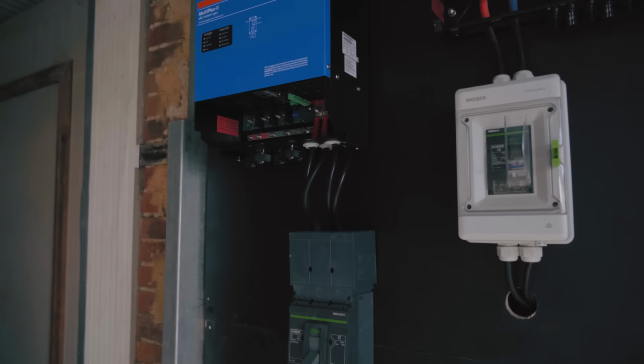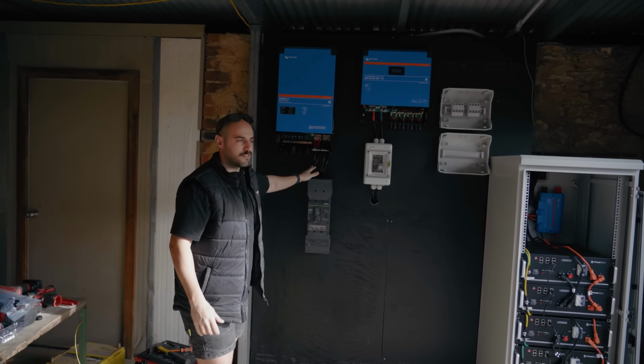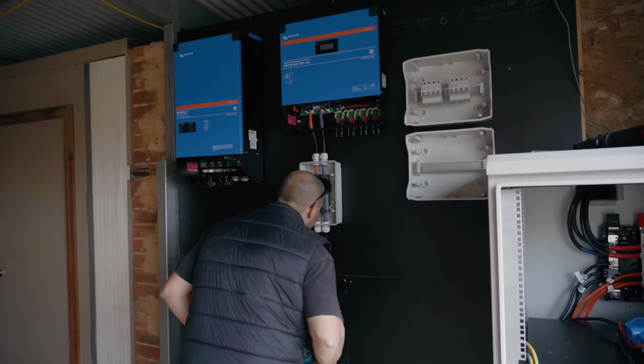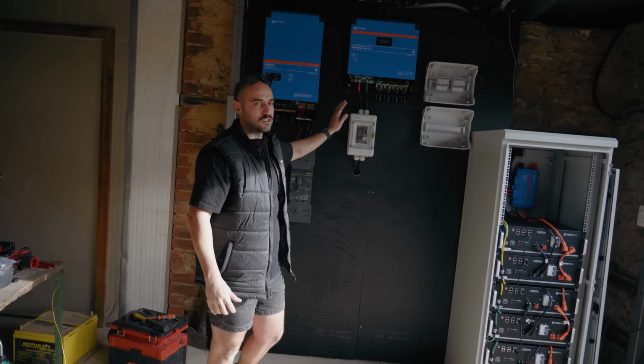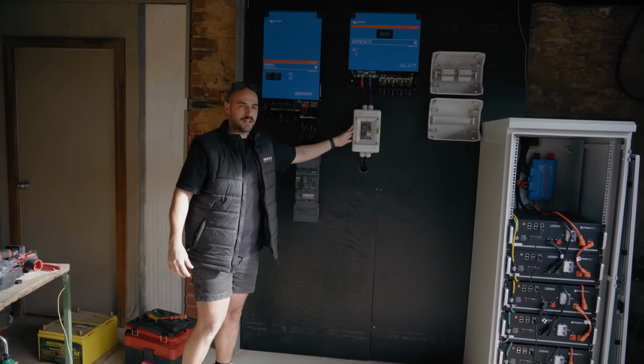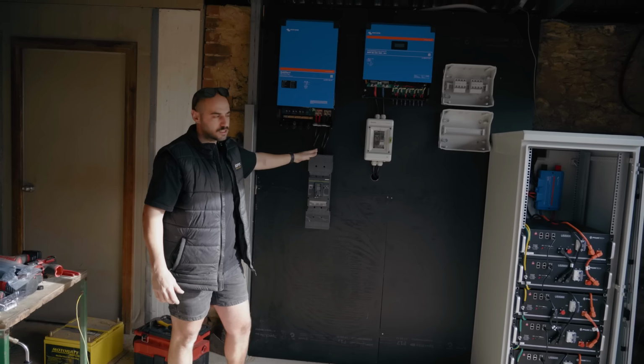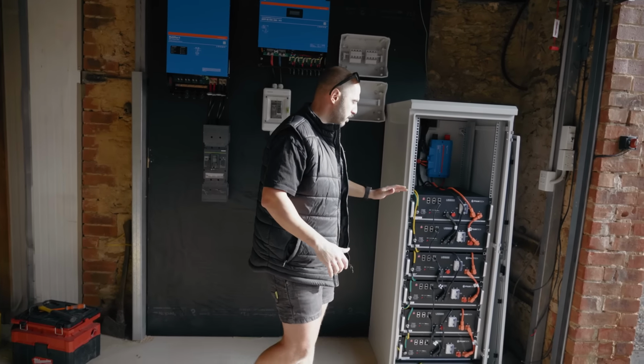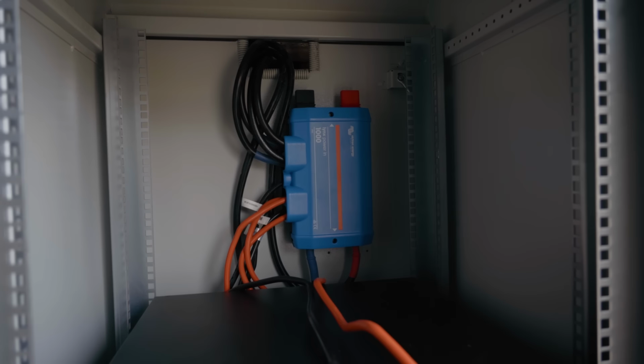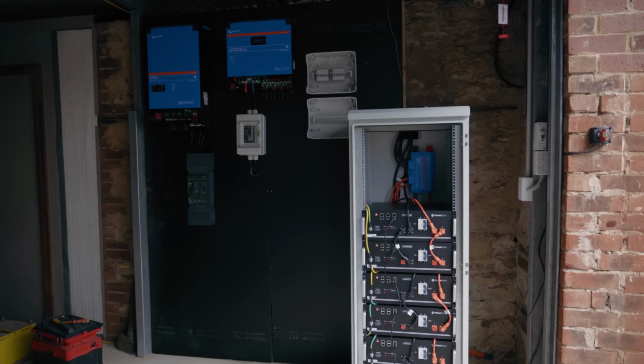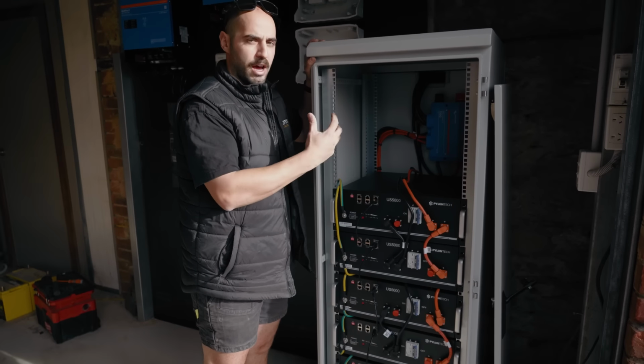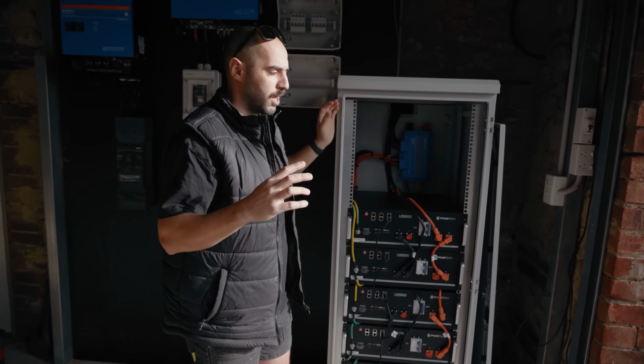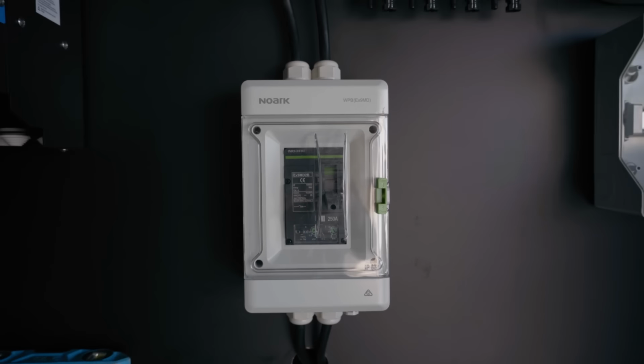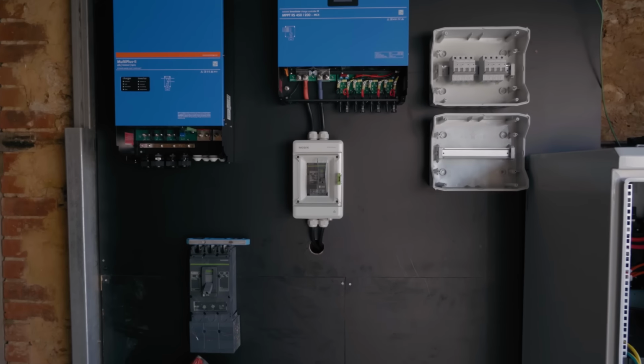We finished wiring the MultiPlus battery cables. We ran two pairs of positive and negative 50mm flexes to that, as well as to the MPPT, and a pair just to the MPPT. We've run all that back into the battery cabinet and tidied it up. In here we've put our Lynx power in, which is one big bus bar that takes all the power from the batteries, the MPPT, and the MultiPlus into one big DC distribution point, so this will distribute power in and out from the battery stack.